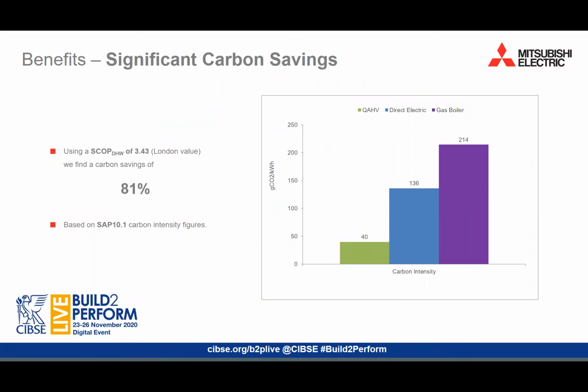The result of this high seasonal efficiency is significant carbon savings. By using the figures for primary fuel from SAP 10.1, with mains gas being at 210 and grid electricity being 136 grams of CO2 per kilowatt hour, we find that the carbon intensity for QAHV technology is just 40 grams of CO2 per kilowatt hour delivered. That means that right now, a huge 81% saving can be achieved against gas boiler technology with a COP of 0.98.